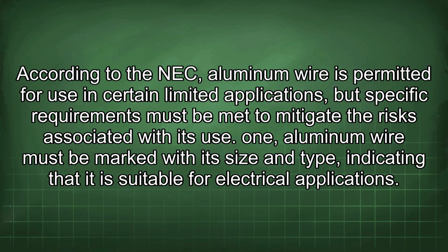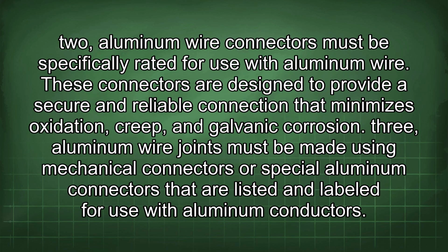1. Aluminum wire must be marked with its size and type, indicating that it is suitable for electrical applications. 2. Aluminum wire connectors must be specifically rated for use with aluminum wire. These connectors are designed to provide a secure and reliable connection that minimizes oxidation, creep, and galvanic corrosion.